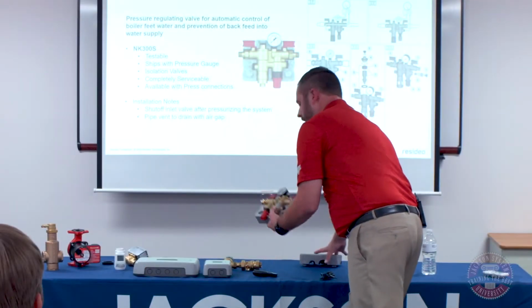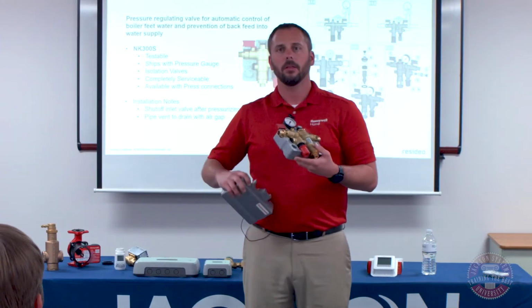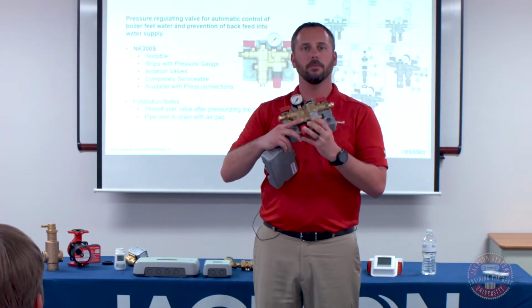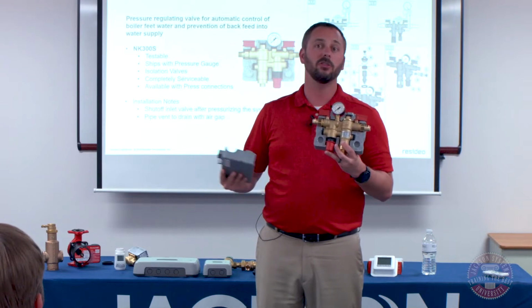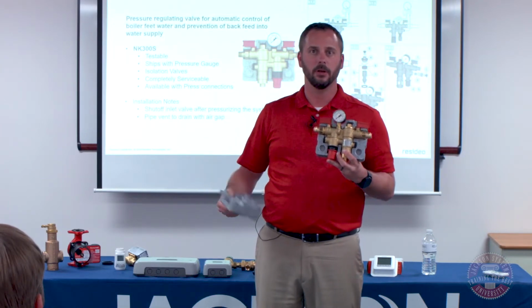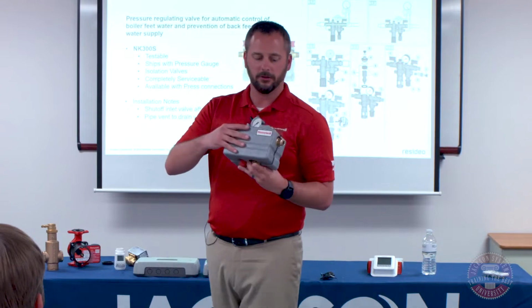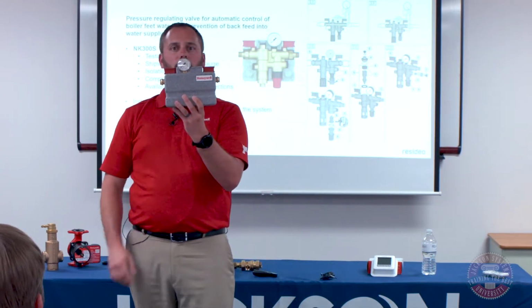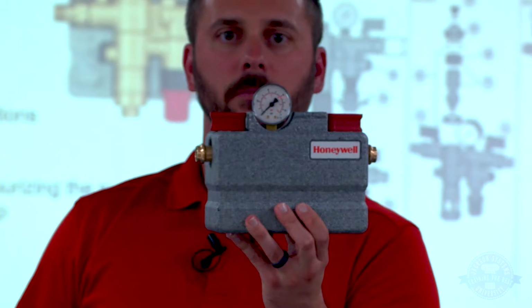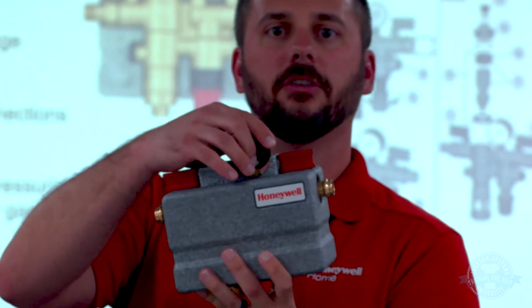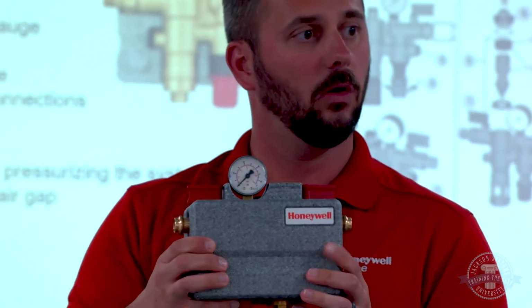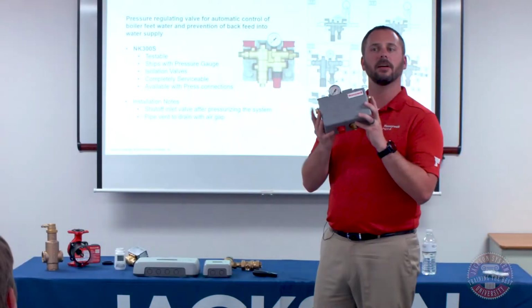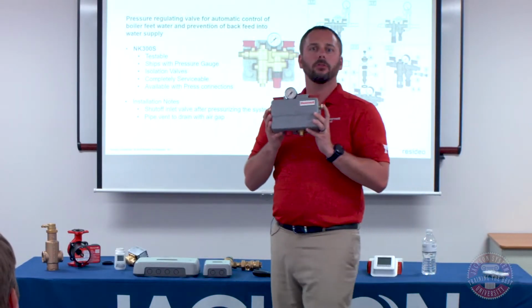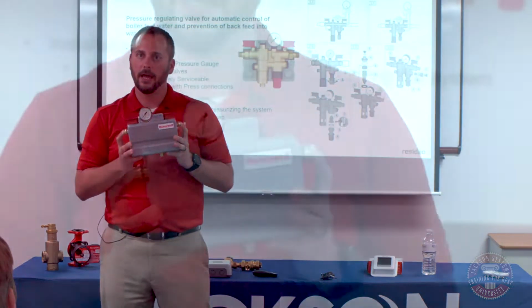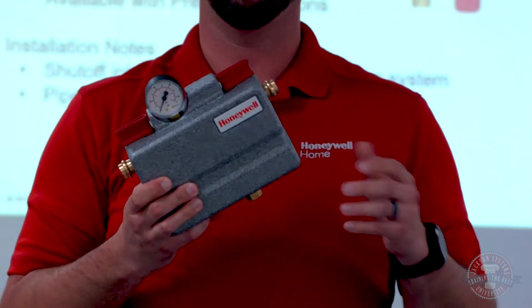And it also ships with this plastic housing. This comes this way from Europe, from our European division. You have the option of either using this or not using this. This isn't just packing material. This is actually engineered to plug together and be one solid block against the wall. It also can be operated either way. Just make sure you follow the direction of flow. And we make it in several different connection types. So our most common is just sweat and thread on this. So it ships with both sweat and threaded tail pieces in the box.